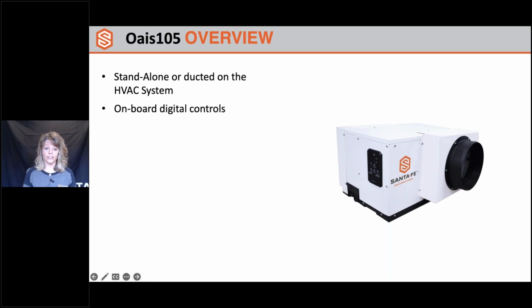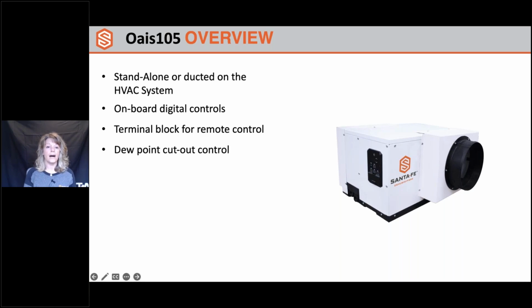We have our onboard digital controls. This is the first unit that we have with that. A terminal block for remote control. So again, this can be ducted to an external controller, more for the HVAC side, but also for those that want more control of the unit, maybe in a crawl space application. Dew point cutout control, which will help minimize how often the dehumidifier goes into defrost, which will extend the life of the dehumidifier.